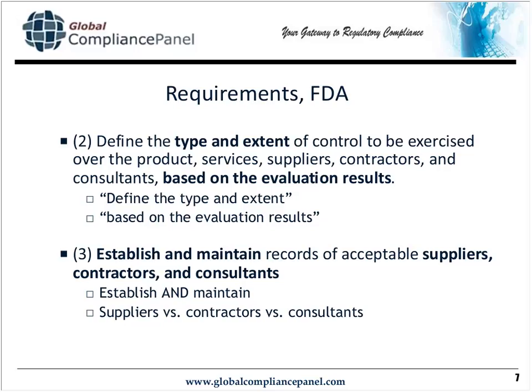I'll talk about this again, but a system that I've used for many years is when I assess a supplier and they have an ISO certification, an appropriate ISO certification. If I'm using a manufacturer, I'd like to see ISO 13485 or 9001. If I'm using a calibration lab, I'd like to see ISO 17025. If I'm using a sterilizer, I'd like to see ISO 11135.